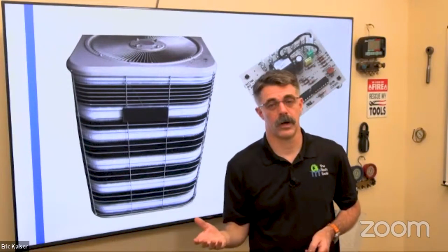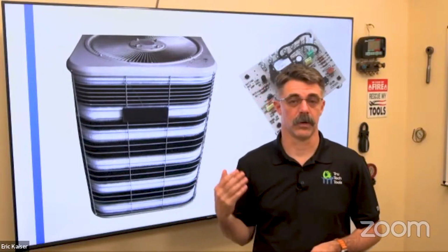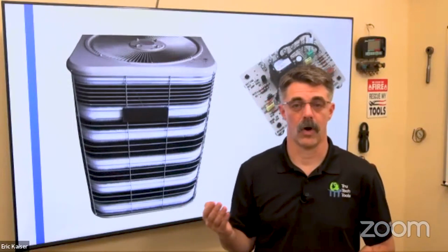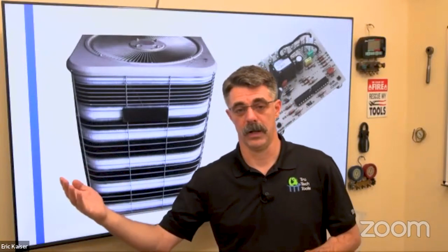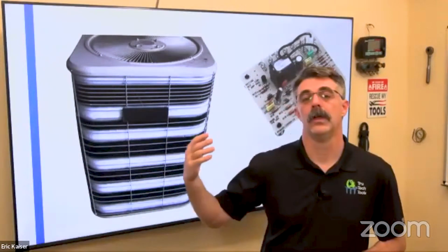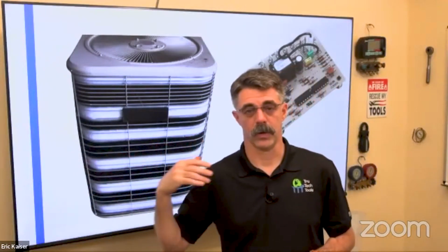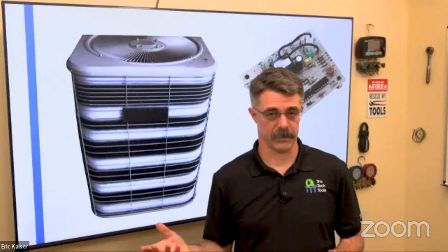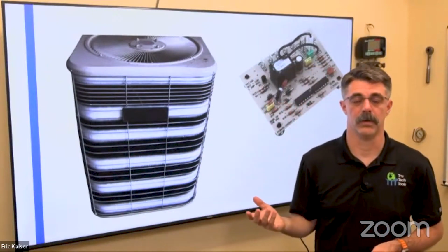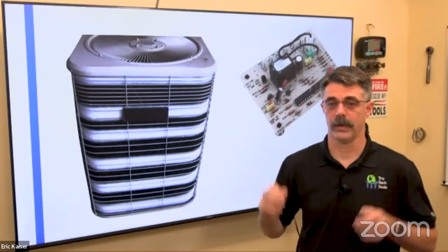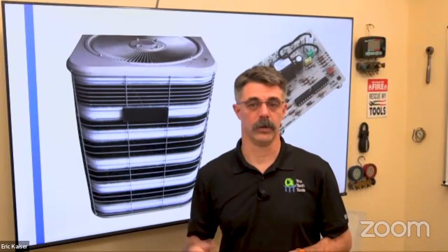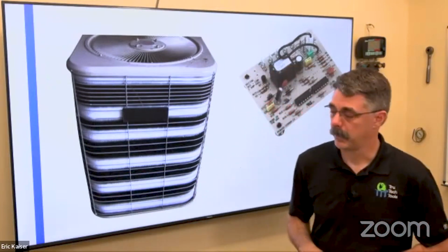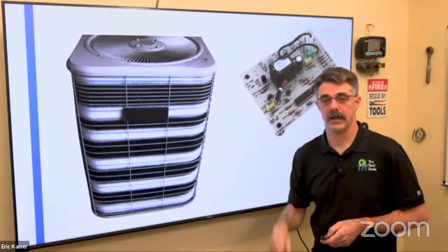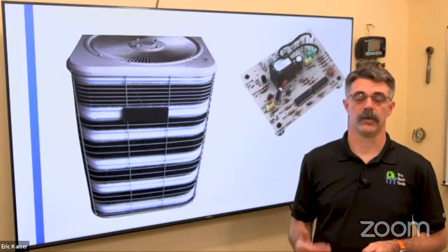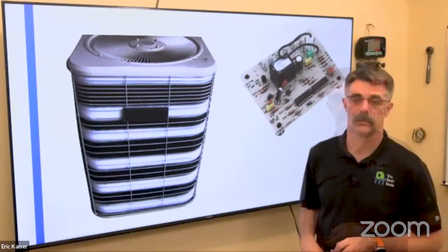Now, demand defrost typically uses less energy, runs less defrost cycles, because often people will set up defrost cycles to bring on some heat inside the house so that we don't get what's called cold blow onto people if there does happen to be some air blowing at people. If people don't feel like it's cold in the house for a couple minutes while it goes through a defrost cycle. But I highly recommend demand defrost boards versus time and temperature board.